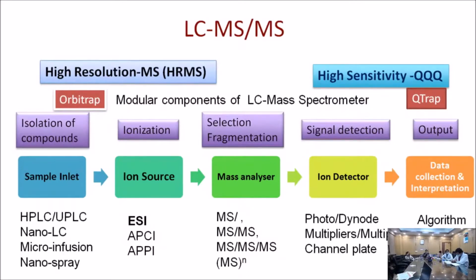First, when the sample is inserted inside, through the sample inlet, you can inject it directly, or use it by HPLC or UPLC, nanoLC, nanospray, or flow infusion, using a micro syringe pump. If it is a pure compound, you use an infusion assembly, or you use HPLC to partially purify a compound from all others, so it can be inserted inside the mass spectrometer.